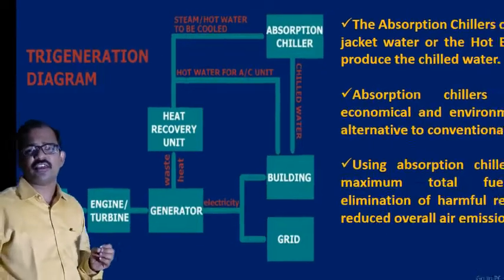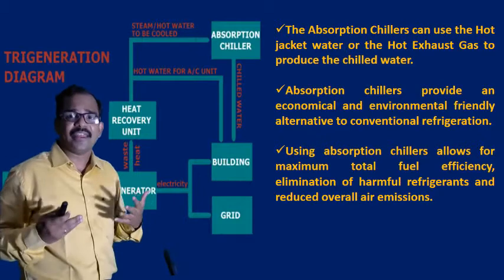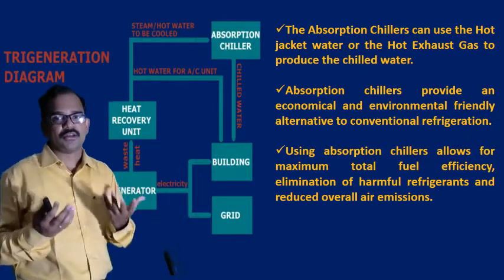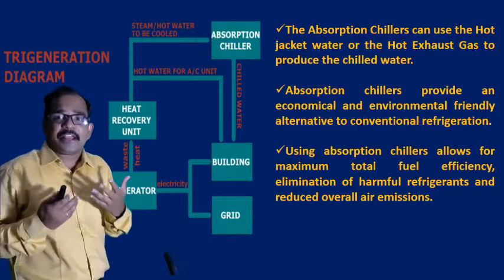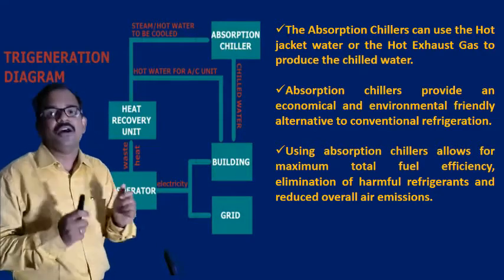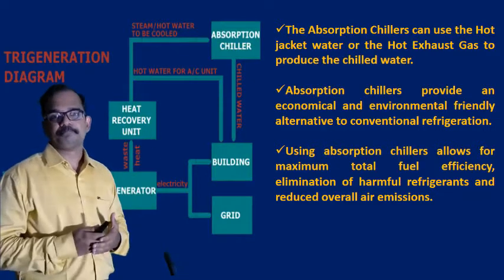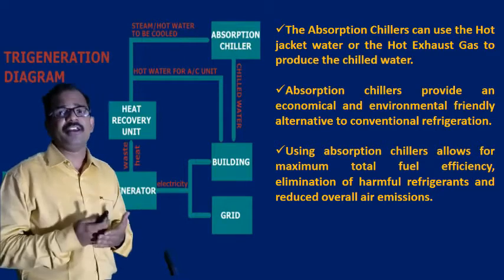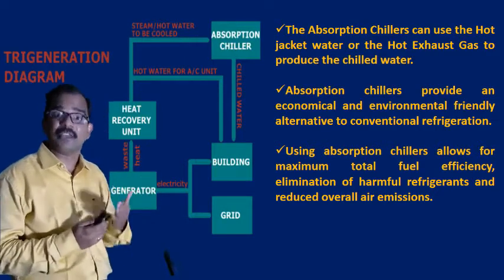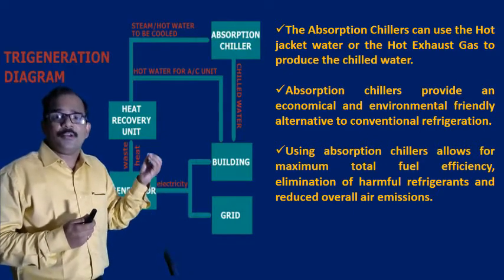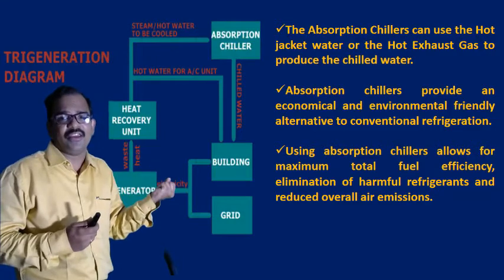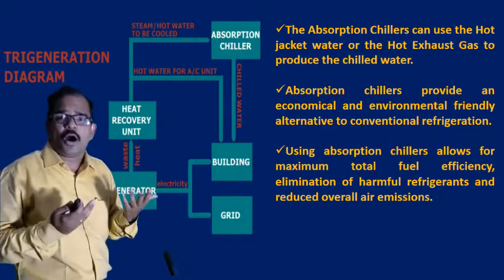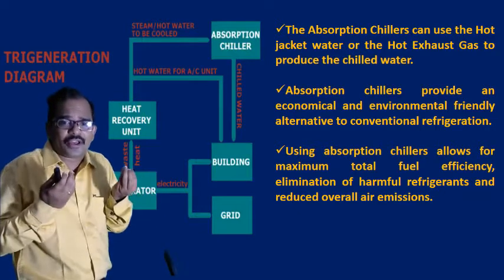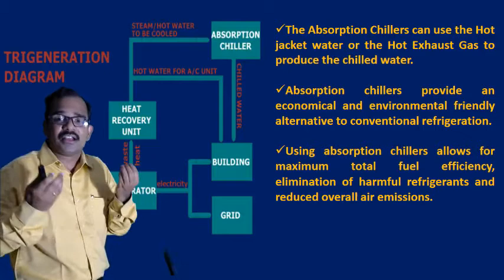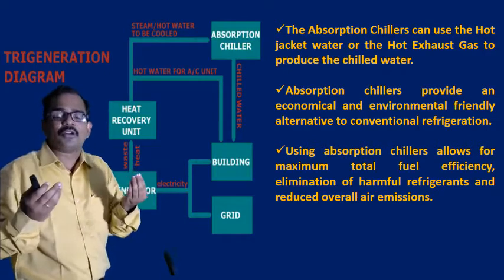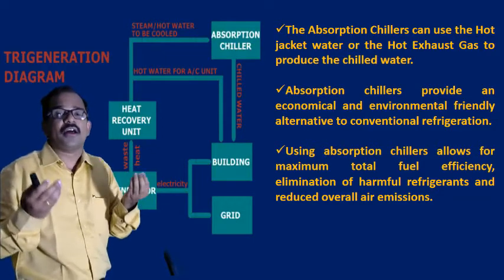The absorption chillers can use the hot jacket waters or the hot exhaust gases to produce the chilled water. The absorption chillers provide an economical and environmentally friendly alternative to conventional refrigeration systems. Why are they providing a sustainable alternative to the conventional way of refrigeration? Because the absorption chillers allow for maximum total fuel efficiency, as well as eliminate the harmful refrigerants and reduce the overall air emissions that come when the normal or the traditional refrigerants are used in the system.